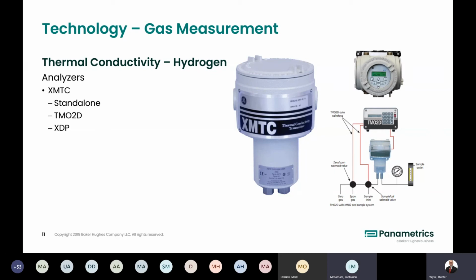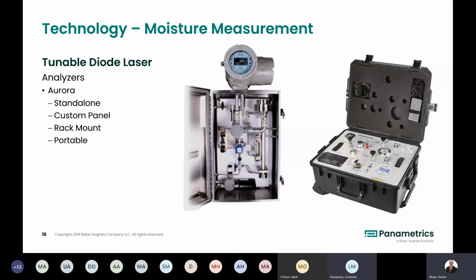Another thing as well, speaking of the issues that we could see on ALOX or even the gas analyzers, Lachlan, is there anything in particular that you want to point out from the moisture measurement on the Auroras? Potential ways of identifying failures, or anything else? Yeah, well, the Aurora is a fairly intuitive analyzer in that if there's something wrong with it, it'll tell you. There are a large number of error messages that will scroll across the top of the screen. I suppose the most common one that we would see is a weak signal error.